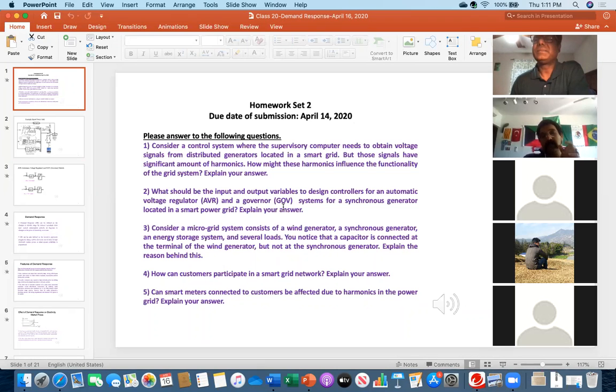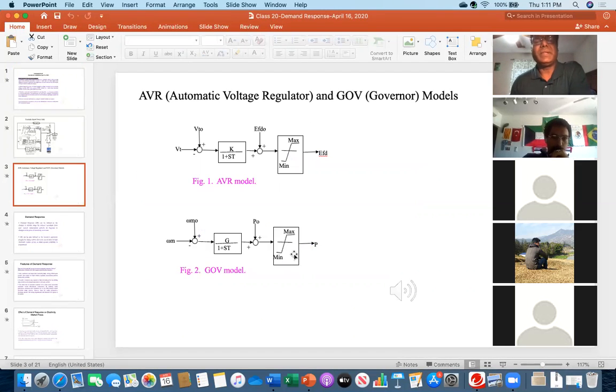Exactly. So basically this is like a valve system. Therefore, when I am controlling by looking at the speed, I am controlling the mechanical power, meaning I have to open and close the valve, control the flow of gas, control the flow of steam. That is the meaning. Or in case of the nuclear turbine, like uranium and plutonium, that is the meaning. So ultimately, by opening and closing the valve, you control the input, and that controls the mechanical power, which ultimately controls the shaft speed.